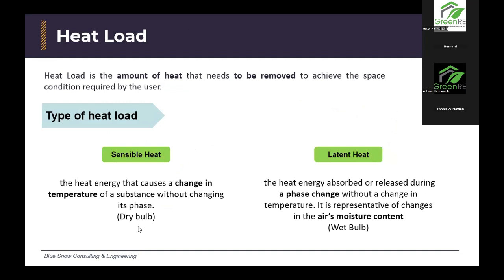The next one is about heat load. Heat load is the amount of heat that needs to be removed to achieve the space condition required by the user. This is the term of heat load used in HVAC. There are two types of heat load. The first one is sensible heat, which is heat that causes a change in temperature of a substance without changing the phase. The phase means liquid, gas, or solid. So this is the heat required to change the temperature only.